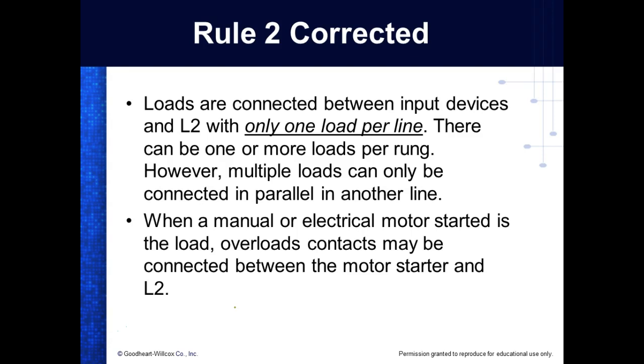So what they do on these motors is the overloads are going to be external. So this motor starter that you saw here, this motor starter is designed to run a dual voltage motor. So what that means is I can change the overloads out on them for different motors. Now, what's nice about solid state overloads? It's going to have a little wiper on the side that you can do what? You can change the electronic overloads. We don't, but these heaters, we'd have to change them out for a different motor, or we could use the same overload, but we use different heaters for different voltage motors.